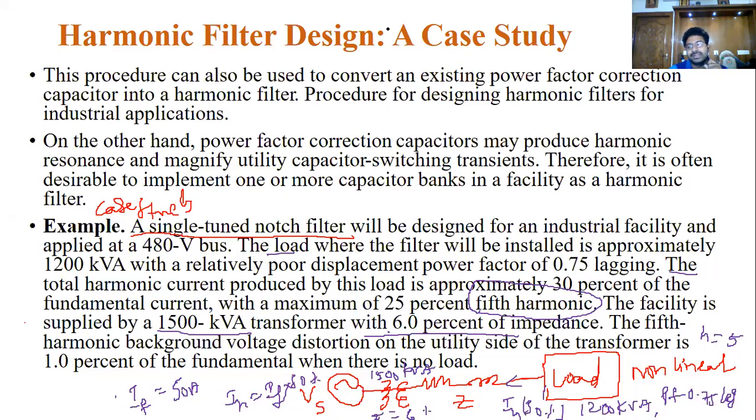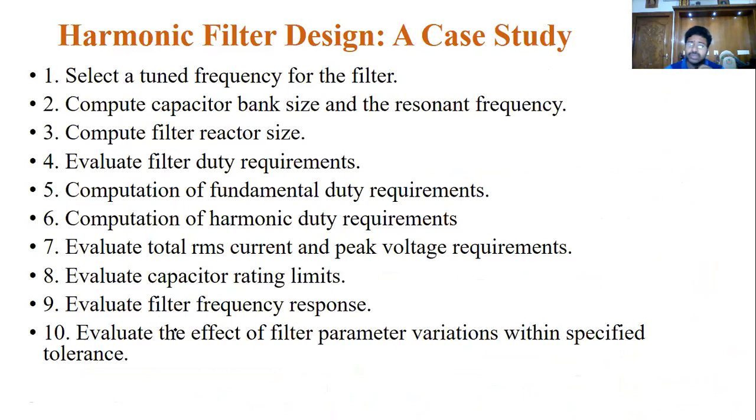Here we are going to design a single tuned filter. We consider the industrial application, because you know that industrial consumers can be penalized for injecting harmonics into the system. That's why they must install harmonic elimination devices, that is, these types of filters.